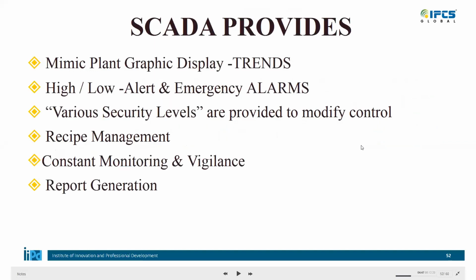For small machines it could be a HMI, but for big plants or big machines it will normally be what we call a control room where the SCADA is set up. The main advantage of using SCADA is you can have real life models of your plant inside it. You can monitor, control, and give supervisory commands. For complex machinery, SCADA can also be used for direct control.